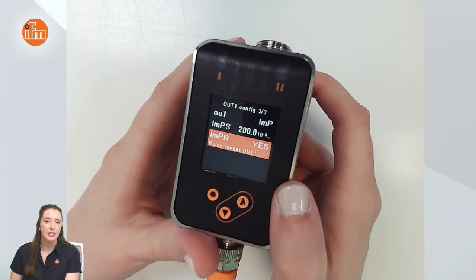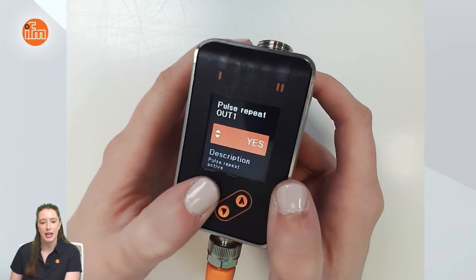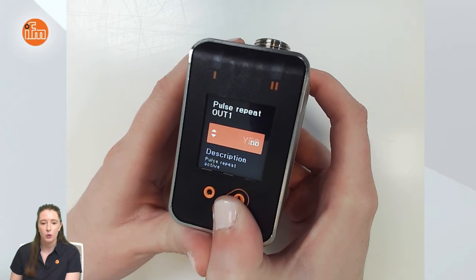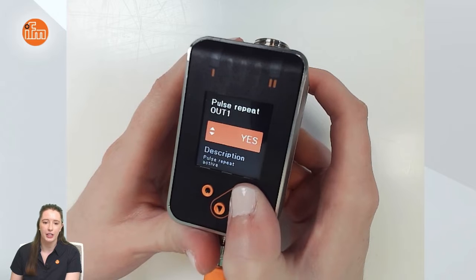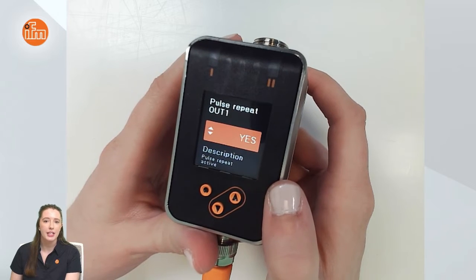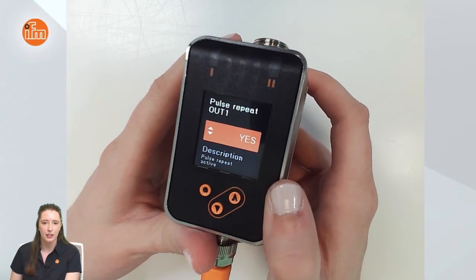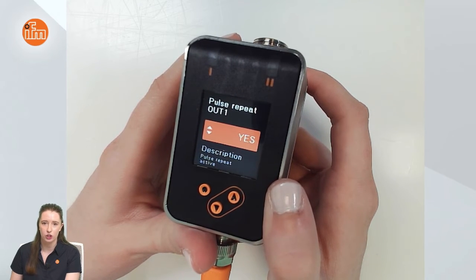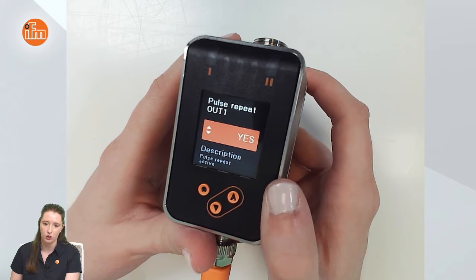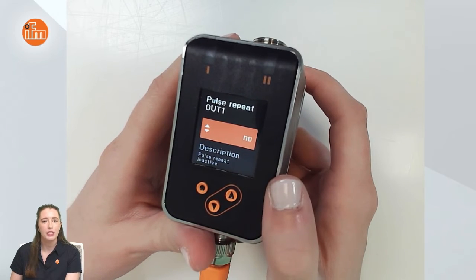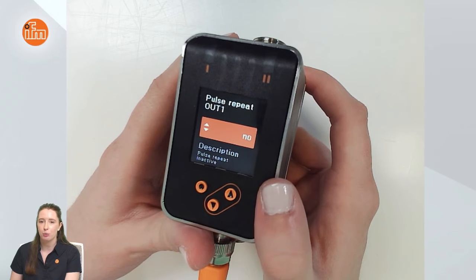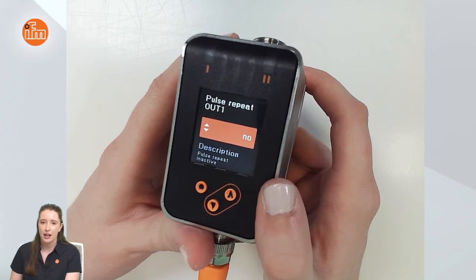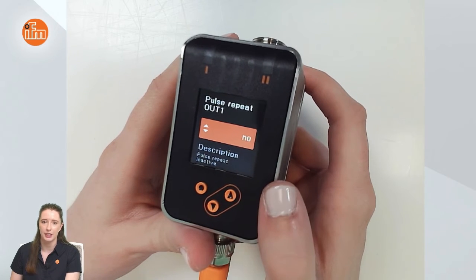Next you can see IMPR and it is set for yes. If you hit the enter key and hold down either the up or down arrow key, the bar will load and you can toggle it for either yes or no. If you want a pulsed output every time 0.2 gallons has gone through, keep it set for yes — that way you can count those pulses to know the actual totalized value. If you set it for no and set IMPS to, for example, 10 gallons, you would get a single output once 10 gallons is reached and it would stay high until you reset the sensor.